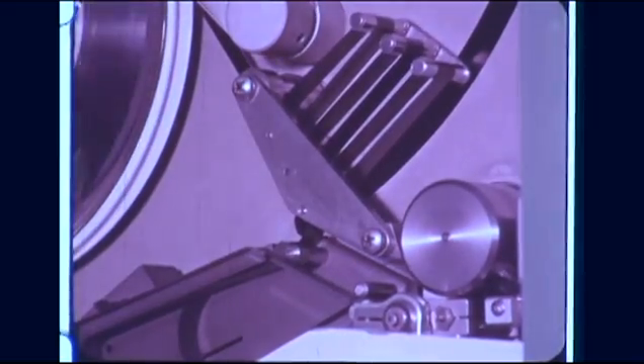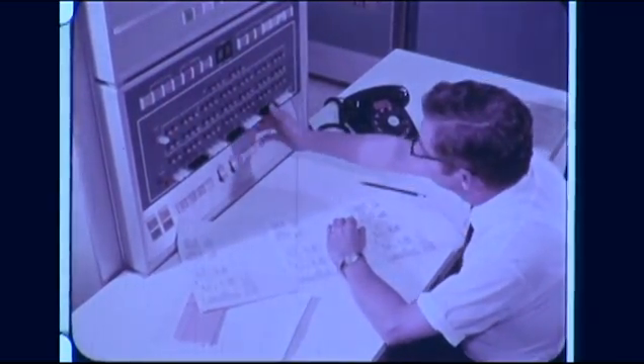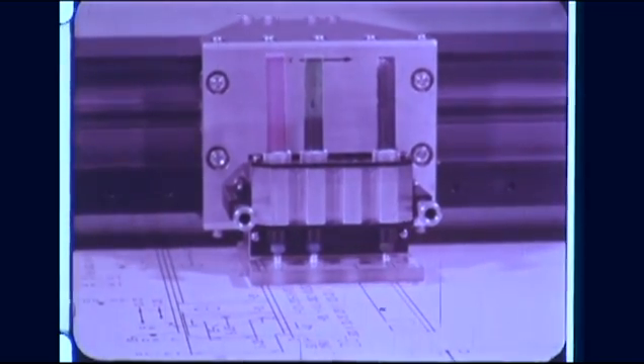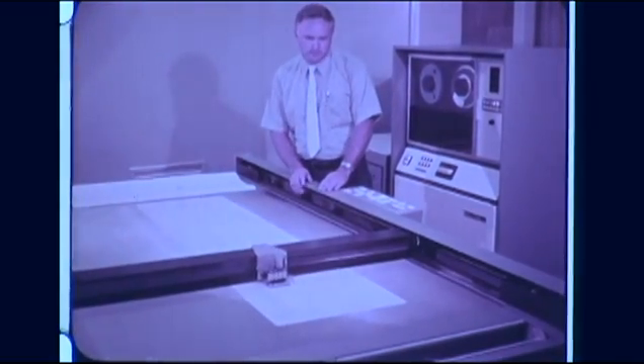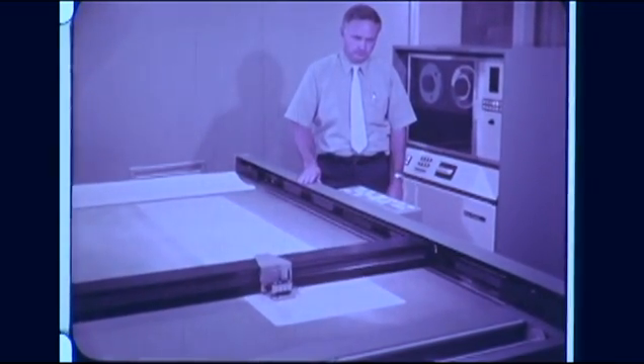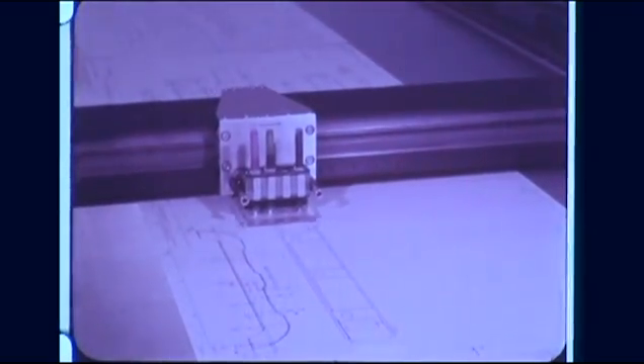In the first phase of this integrated short circuit program, sophisticated computer programs were developed to calculate the detailed forces generated in transformers by through-fault currents and to predict the effects of these forces on windings and insulation structures. Other programs were developed to explore the advantages of different winding and tap arrangements on individual transformer designs, and still others to design winding insulation and clamping structures to reduce the effects of the forces generated.